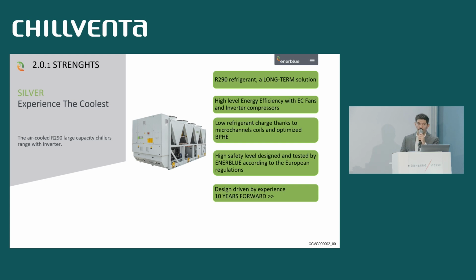Why propane? Enerblue is producing only chillers with propane since about 10 years. We think that propane is an extremely efficient refrigerant, it is nothing new. For us it is our standard, as the EC fans we mount on the unit and inverter-driven compressor. We studied this unit to develop a really efficient product. The microchannel coils and the refrigerant charge were developed to be very, very low. So also to avoid a risk concerning the flammable refrigerant, we made the unit with a very, very low refrigerant charge.